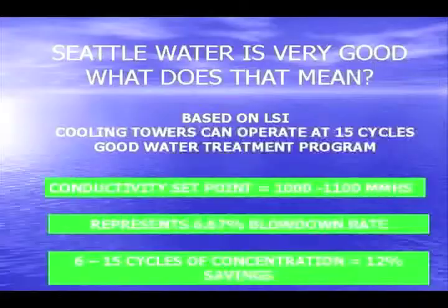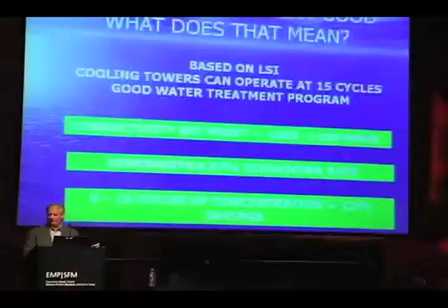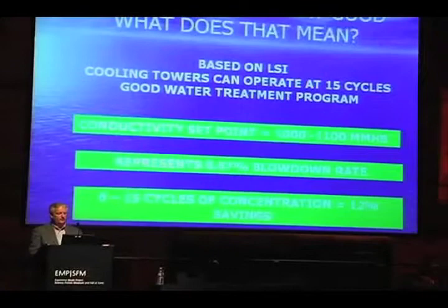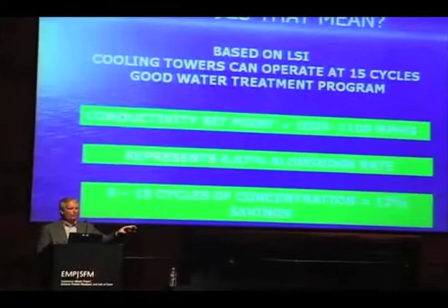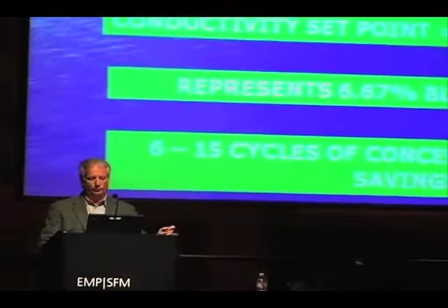I plugged Seattle water into this model and did some calculations to find out where you should be. Based on the LSI, cooling towers in Seattle can operate at 15 cycles of concentration — way out on that graph, which is very good. You need a good water treatment program to prevent scaling, because as you push it out there, you will see some deposition without good water treatment. Your conductivity set points on all your controllers should be around 1,000 to 1,100, unless you have varying makeup source waters. When you go back, check your cooling tower controller and see if it's between 1,000 and 1,100. If it's not, ask your water treatment supplier why.